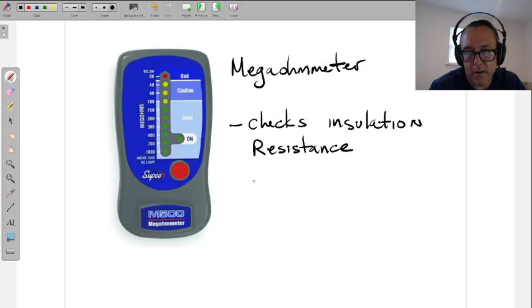Normally, high resistance in a circuit is bad because it means my voltage isn't flowing very nicely. But if I'm judging my insulation, it better have the highest resistance possible. My insulation is the thing protecting everyone from dying, so the higher the insulation rating, the better. That's why on the megohmmeter we want to go into the high numbers, because it's checking insulation.